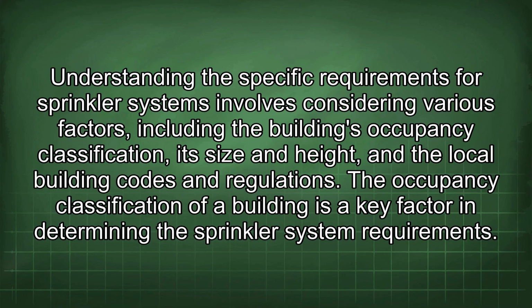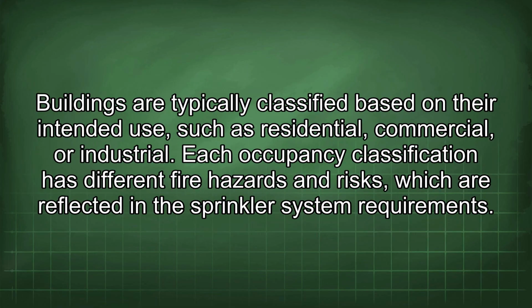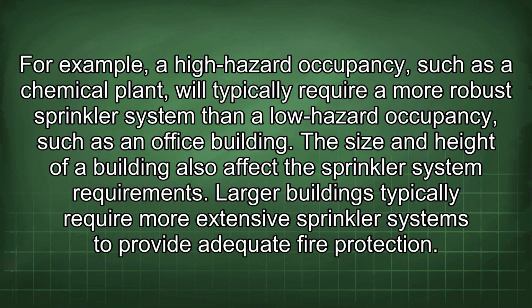Understanding the specific requirements for sprinkler systems involves considering various factors, including the building's occupancy classification, its size and height, and the local building codes and regulations. The occupancy classification of a building is a key factor in determining the sprinkler system requirements. Buildings are typically classified based on their intended use, such as residential, commercial, or industrial. Each occupancy classification has different fire hazards and risks, which are reflected in the sprinkler system requirements. For example, a high-hazard occupancy, such as a chemical plant, will typically require a more robust sprinkler system than a low-hazard occupancy, such as an office building.